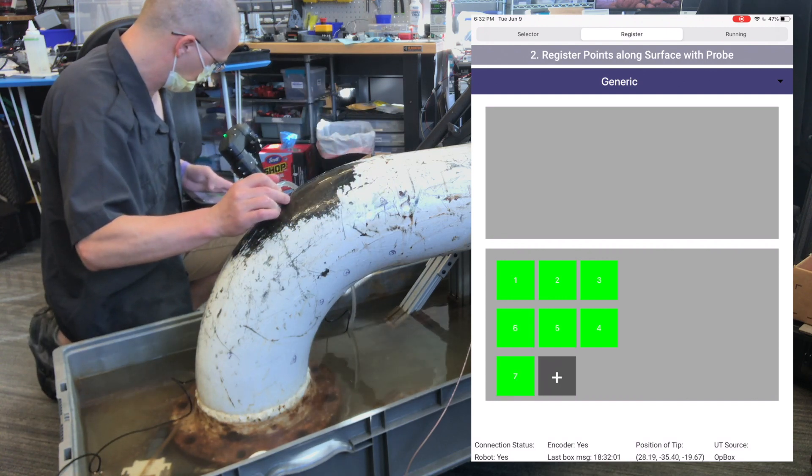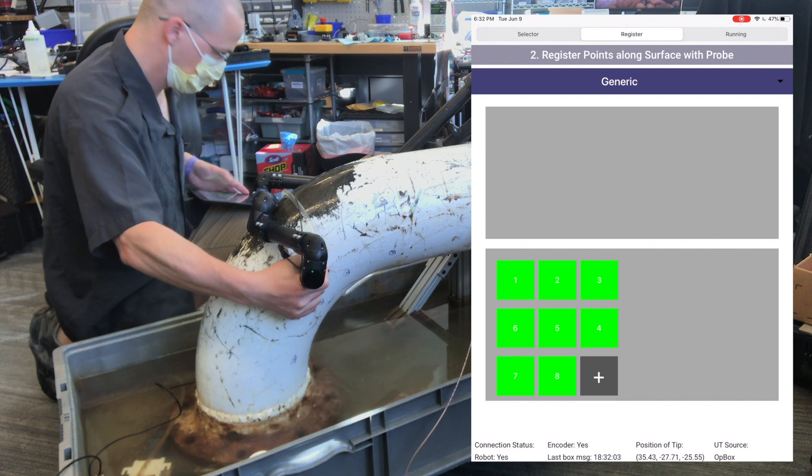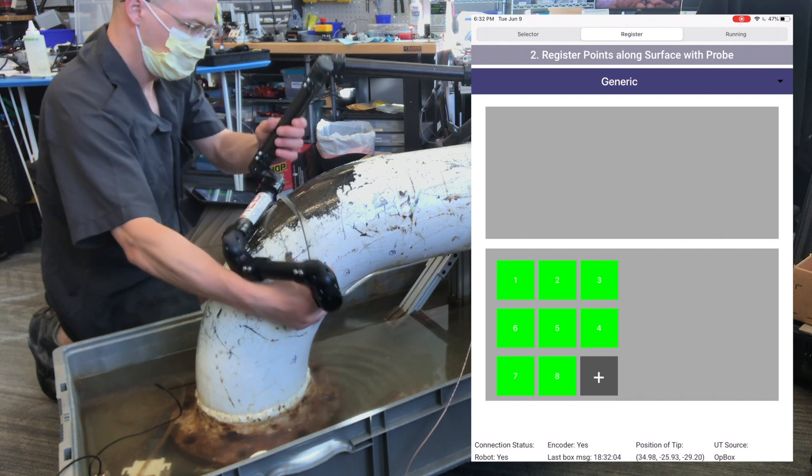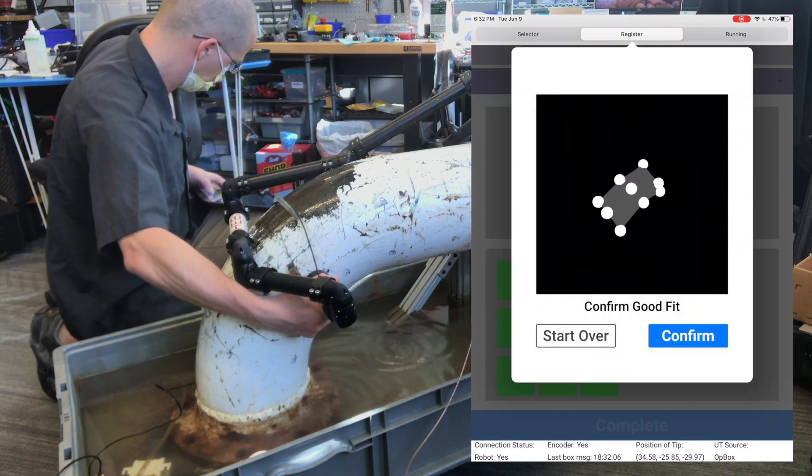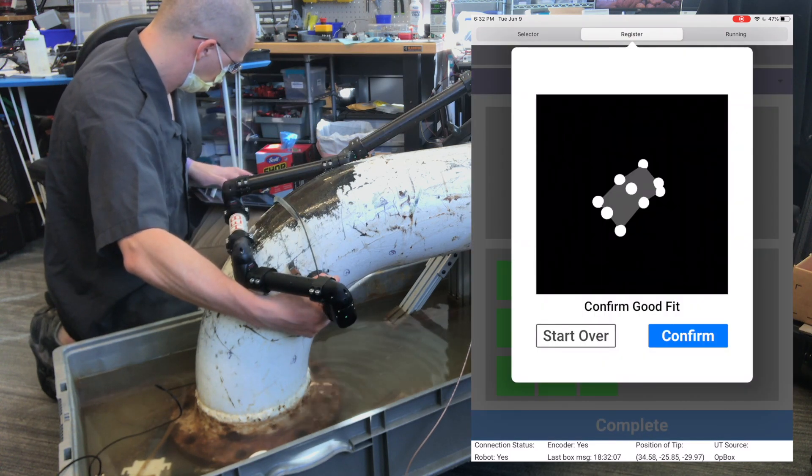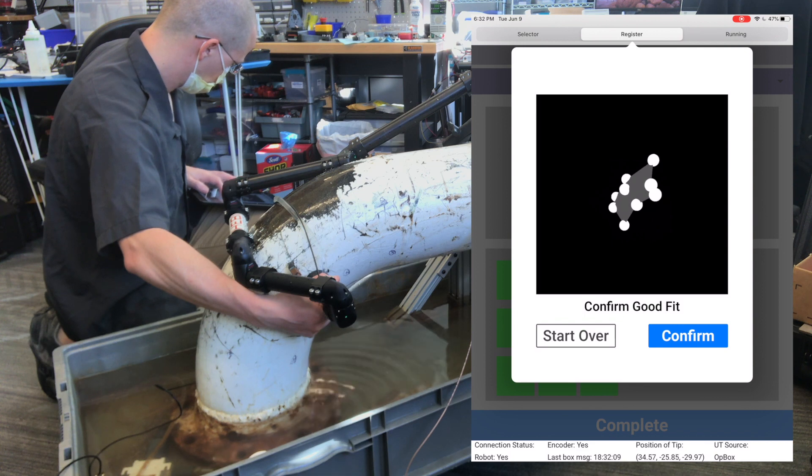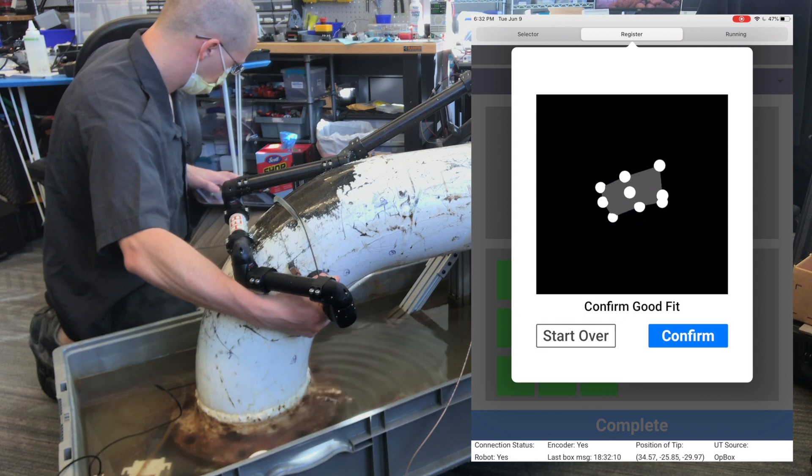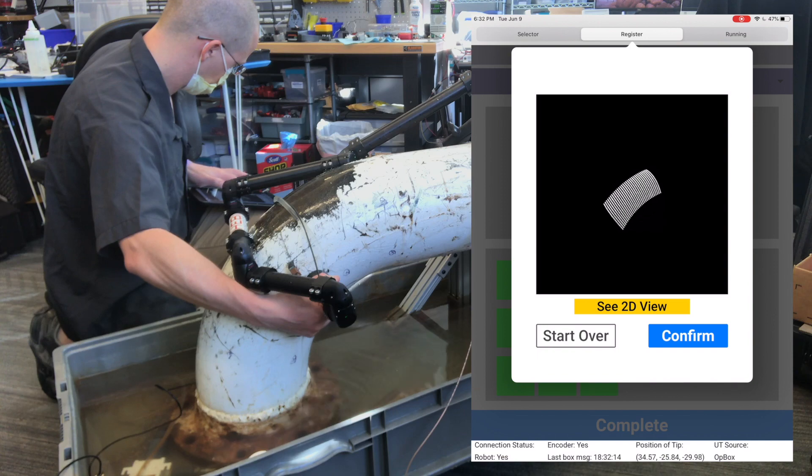With enough points, you can stretch a surface and appropriately grid it to provide an inspection. In this case, I'm setting up a surface that spans part of the straight pipe across the weld onto the elbow, and we'll begin a scan.